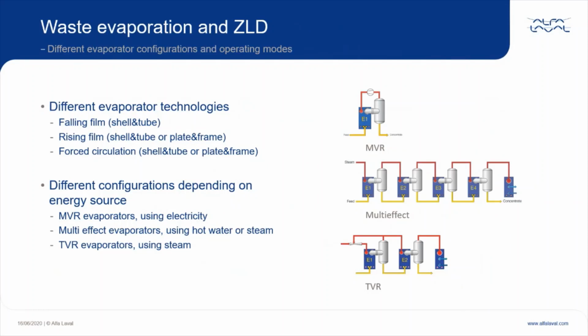When utilizing steam or other thermal source, such as hot water for driving the evaporation process, the most common solution for increased energy efficiency is what is called multiple effect system, using several evaporator modules or effects in series, where the vapors from one effect are used to heat the next effect. This will reduce the steam consumption, and the more effects, the higher the steam saving, but of course at the expense of increased investment cost. Typically, the steam consumption for evaporating 1 ton of water is 1.1 to 1.2 tons steam in a single effect system. And when using multiple effects, this number can be divided by the number of effects to reach the actual steam consumption.